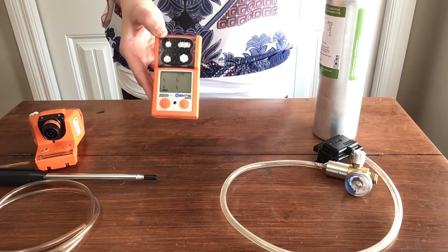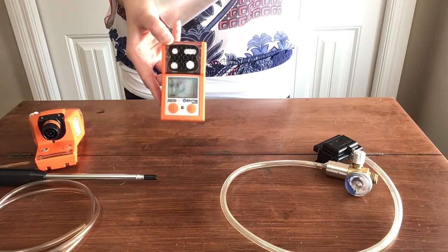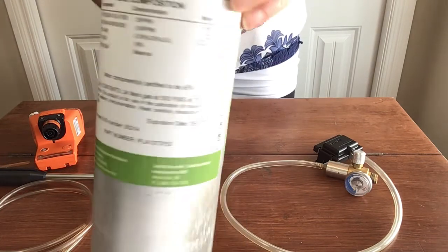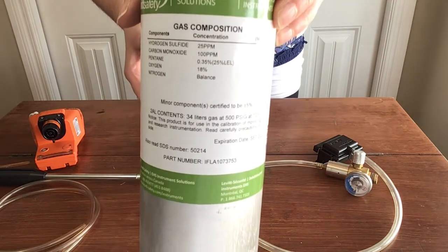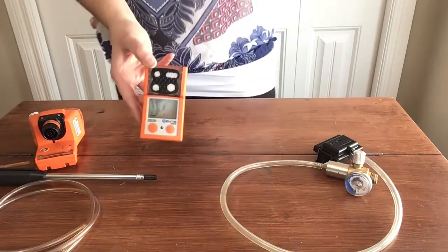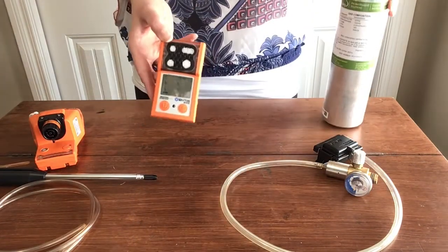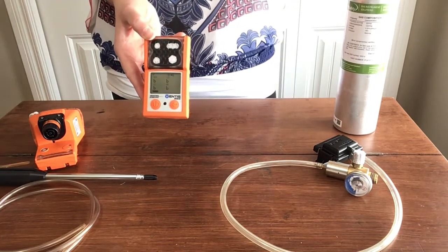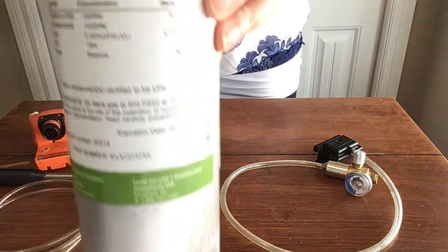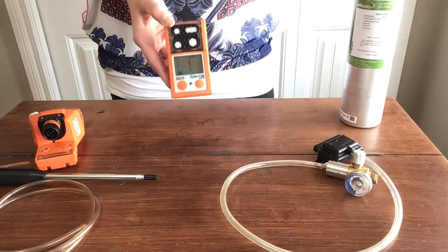So it does not require an annual factory calibration, but the CSA standard does require that these units are calibrated when the bump test results are no longer showing within 100 to 120% of your span gas. So our span gas that we're using here is a combination gas, okay? And it has in it all of the gases that our sensors are reading for, and it tells us how much of each of them are in there. And so when our bump test is no longer demonstrating 100 to 120% of the span gas concentrations here in the middle, then at that point we'll want to do a calibration on this, okay?